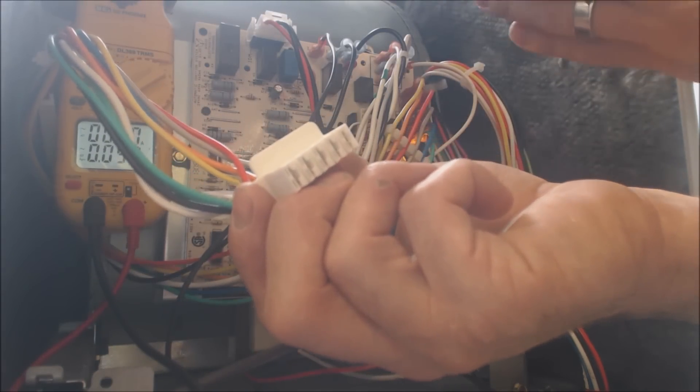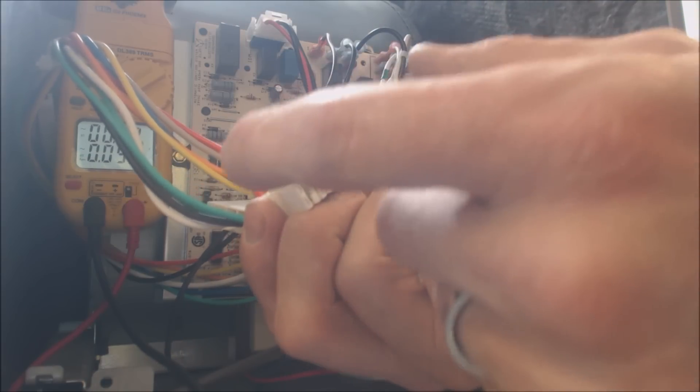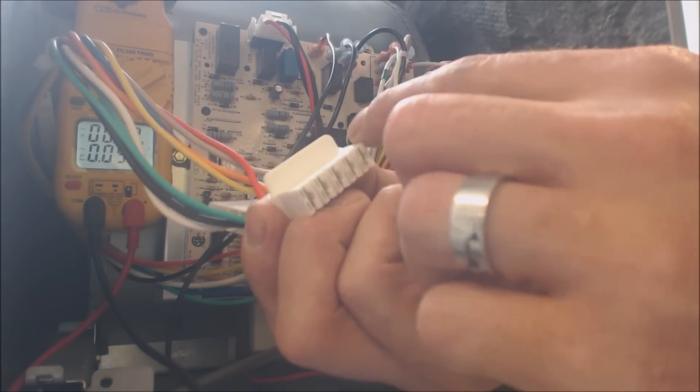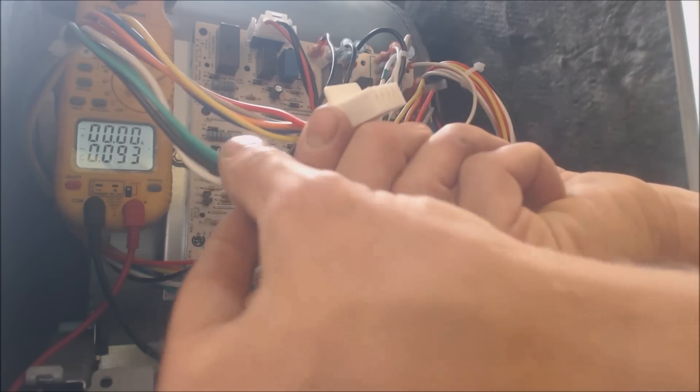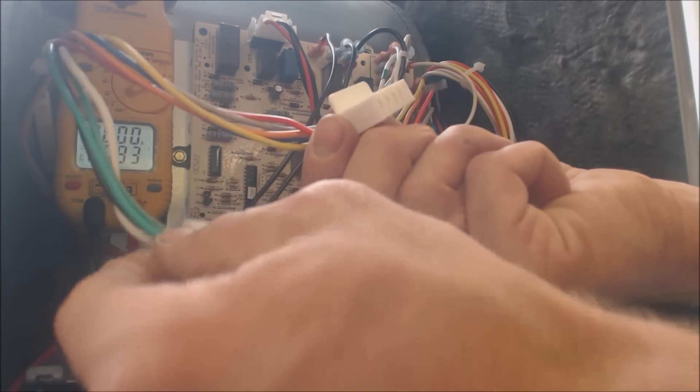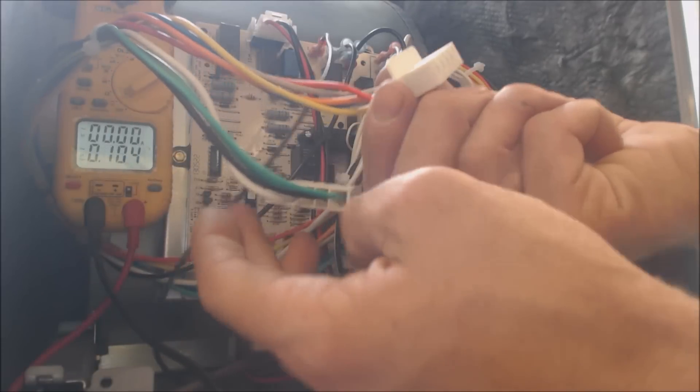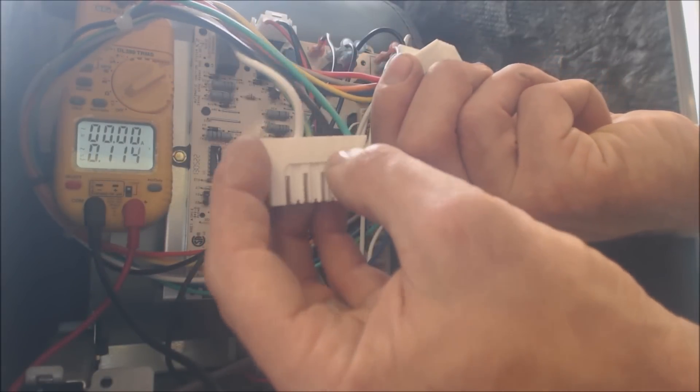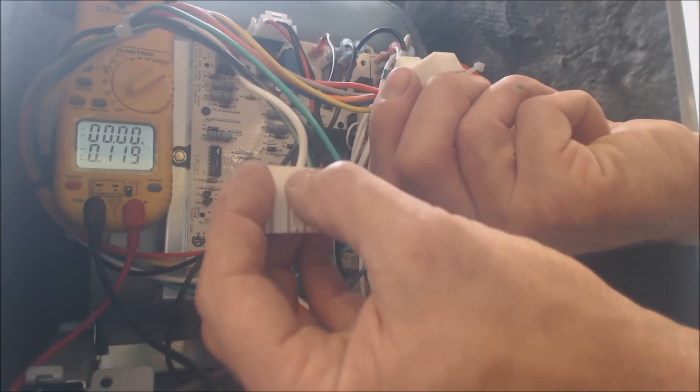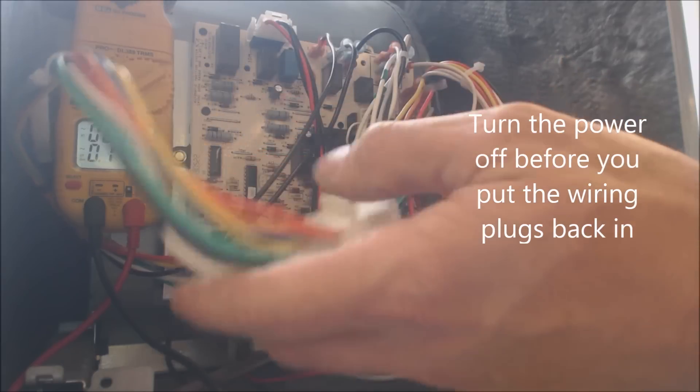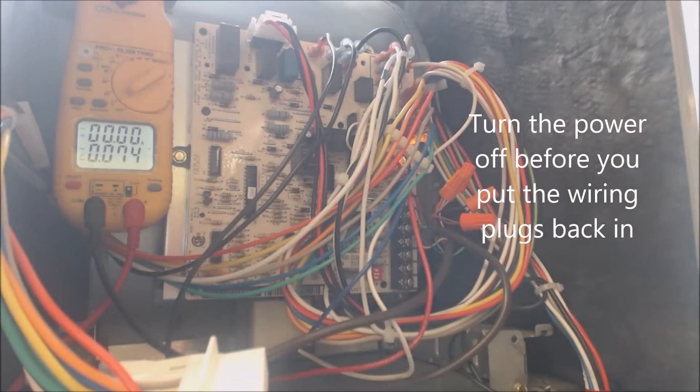But if the blower motor does not work after we just saw that we have voltage going to the gray and coming back out through the green, and you know you have 120 volts from the black to the white wire, then that blower motor is bad. So here we go.